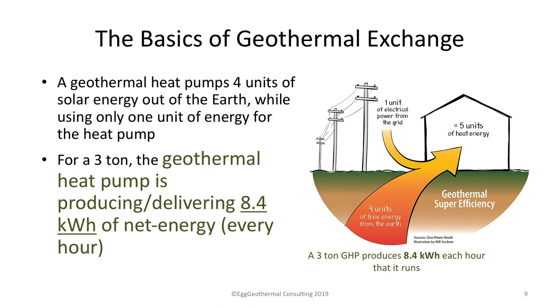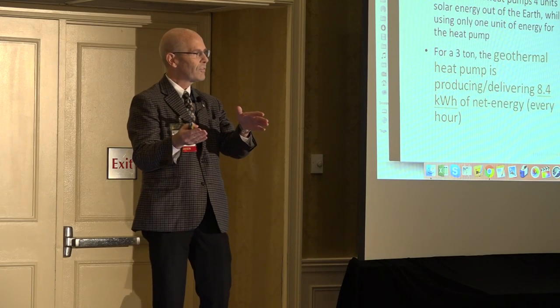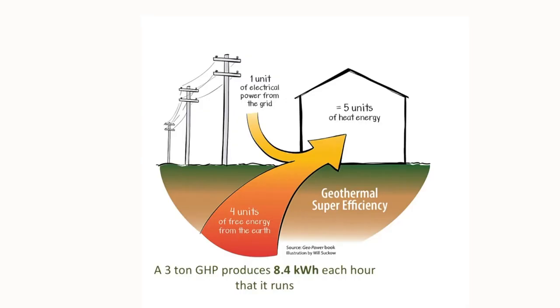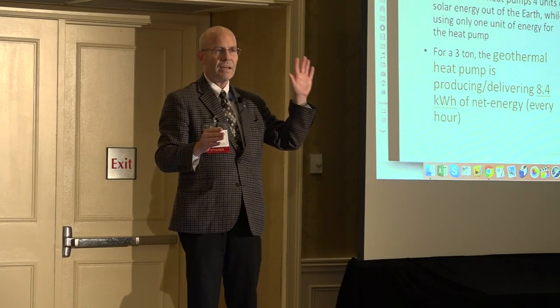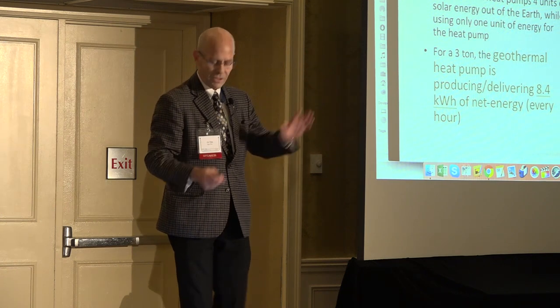I love this diagram: for one unit of electricity from the electric grid going to this heat pump, it uses that unit and pumps four units of heat out of the ground. Add the two together and you get five units of heat in the space. For one unit of energy, you get five units of heat. That's a COP of five — it is 500% efficient. That's how the magic happens.